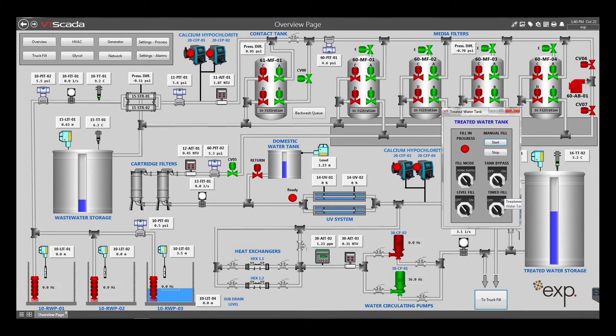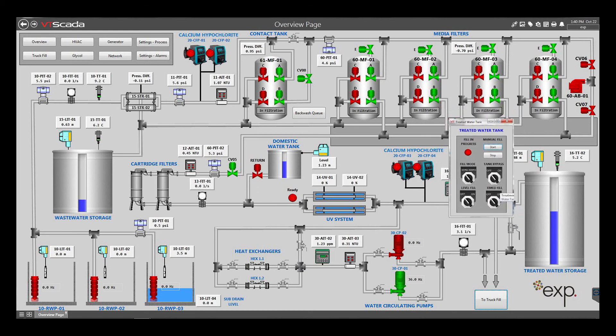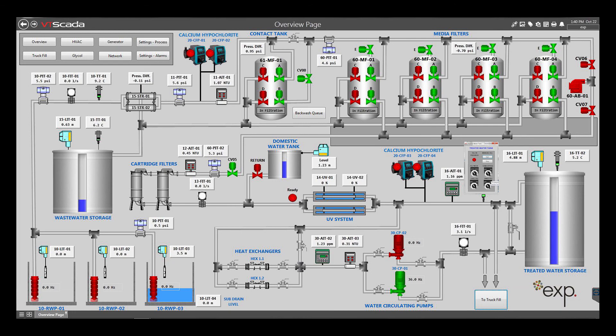The level fill selector switch allows the operator to automatically fill the tank based on level. The timed fill selector switch allows the operator to automatically fill the treated water tank based on time; the fill sequence will start based on time and stop based on level. Set points for this mode are accessible via the settings process screen. The tank bypass selector switch allows the operator to bypass the treated water storage tank. In this mode, truck fills are serviced directly from the end of the water treatment system. The isolation valves on the treatment system first need to be manually manipulated to bypass the treated water storage tank.